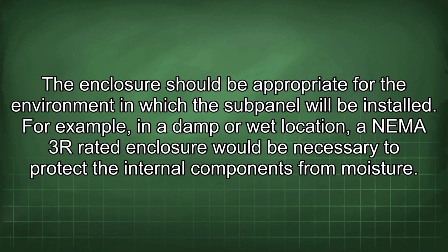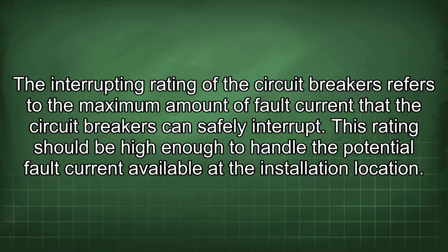The enclosure should be appropriate for the environment in which the subpanel will be installed. For example, in a damp or wet location, a NEMA 3R rated enclosure would be necessary to protect the internal components from moisture. The interrupting rating of the circuit breakers refers to the maximum amount of fault current that the circuit breakers can safely interrupt.